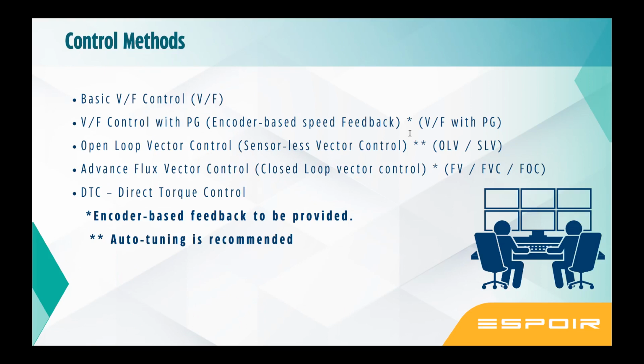Now, the other control method is called the advanced flux vector control or a closed loop vector control. This method is a closed loop control method with feedback. That is the advanced flux vector control mode. Means if you do the tuning, you also give a feedback. So the parameters are going to be very different, unique, and you can set them as per your application. You need to tune it more cohesively to suit the application demand.